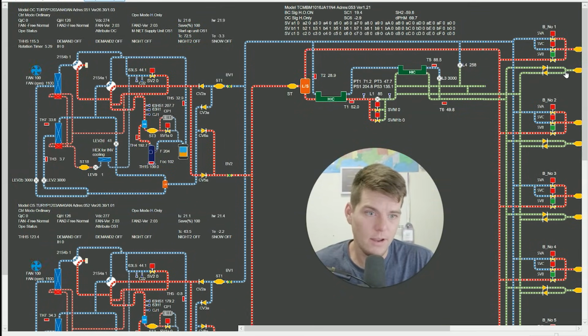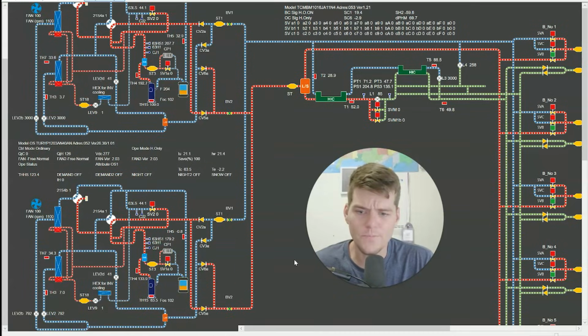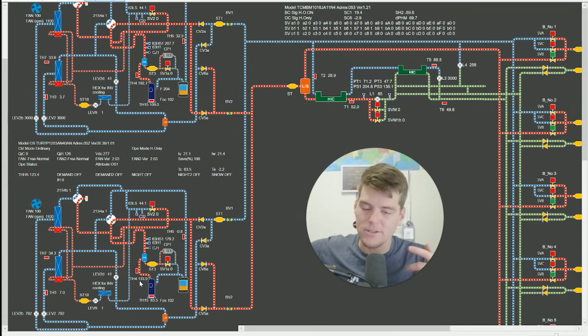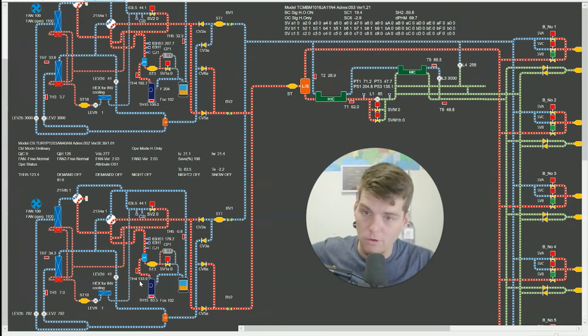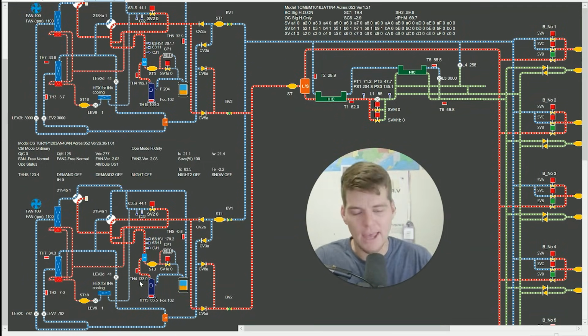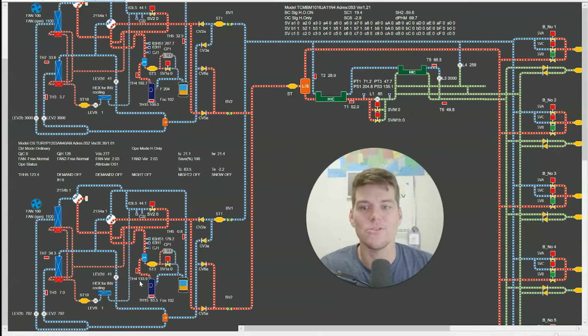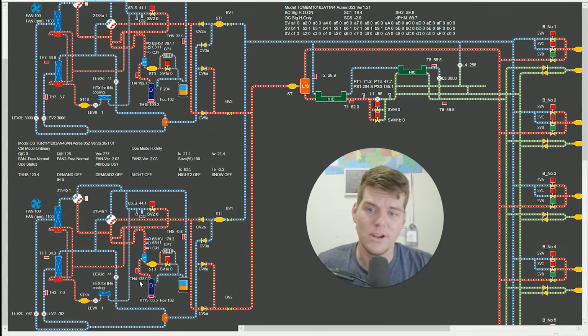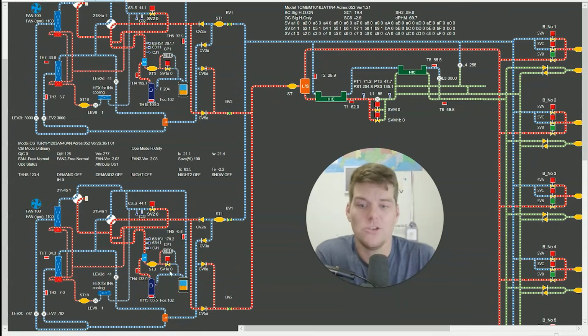Well, my other module, I exit out of my marker here and scroll. You can see here, it shows 133. Wow, significantly lower. Now, your mind may shift and say, okay, well, maybe it's just low on oil, Roman. What if that's the case? Well, let's not jump ahead here. Let's get our 3 corners of the triangle. So we got discharge superheat. Now let's try looking at suction superheat.